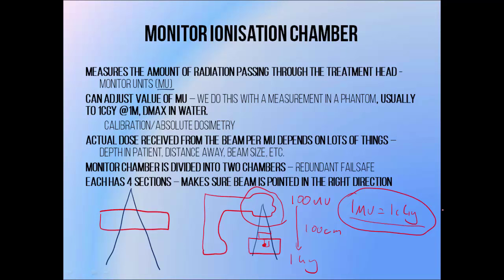Linear accelerators need to use monitor chambers because the rate at which they produce radiation isn't constant over time. So we can't just say we'll leave the beam on for a minute, because we can't accurately know how much dose will come out the other end during that time, the way we would with a radioactive source or a superficial x-ray unit. Determining how much radiation to deliver in terms of monitor units is quite accurate even with an inconsistent dose rate, which is why linear accelerators use monitor chambers when isotope units and many superficial units do not.